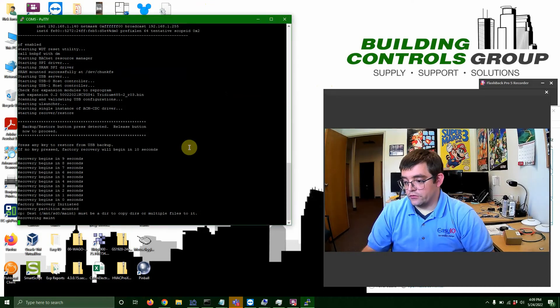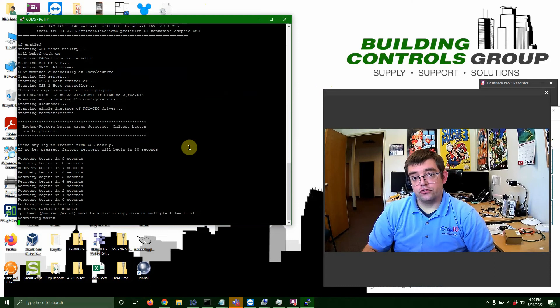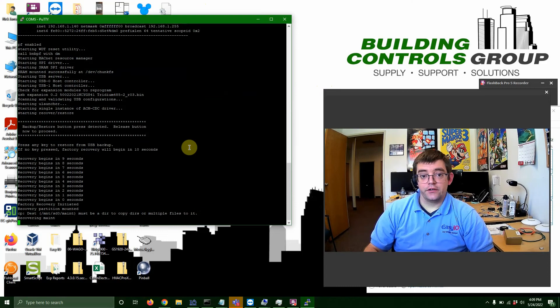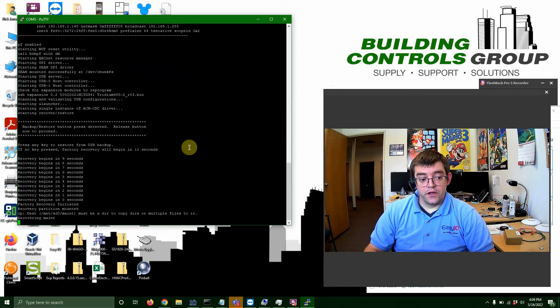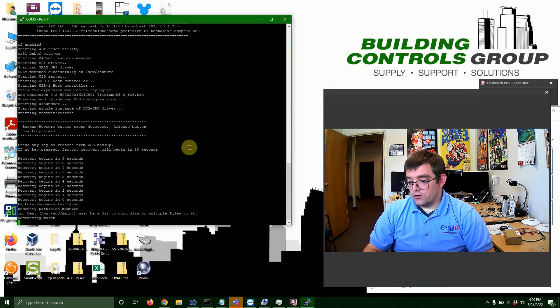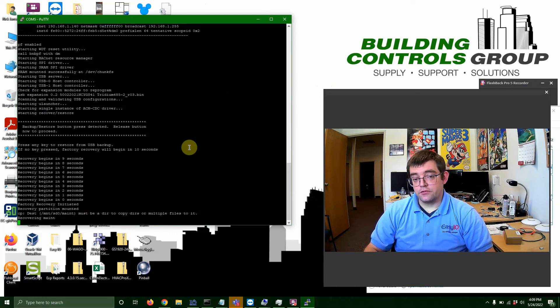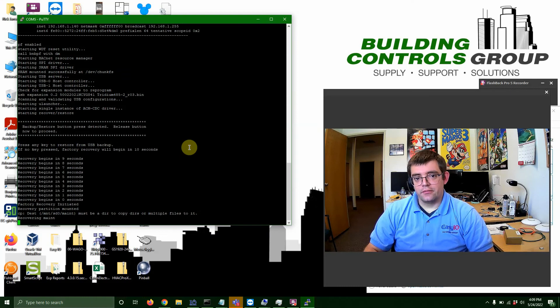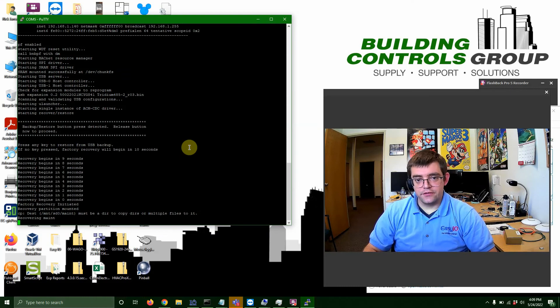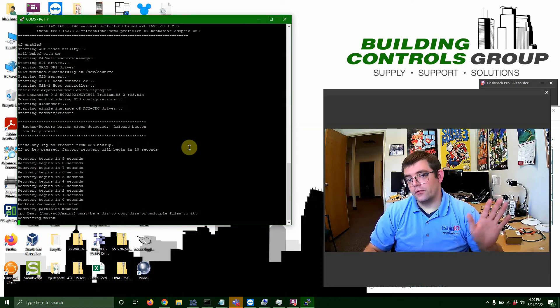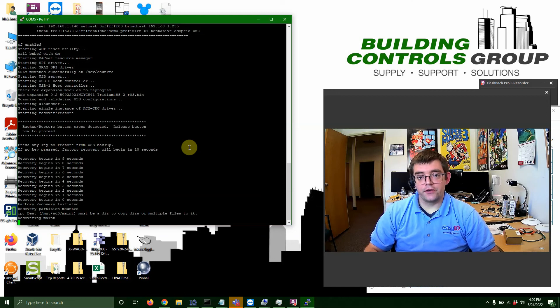So what this is going to do now is it's going to install the clean distribution that was on the factory SD card that's in the Jace. So a few things to note here. This is going to completely wipe your Jace. So IPs, station, the whole thing is going to go away. Basically wipe this thing when it was in the box from the factory.